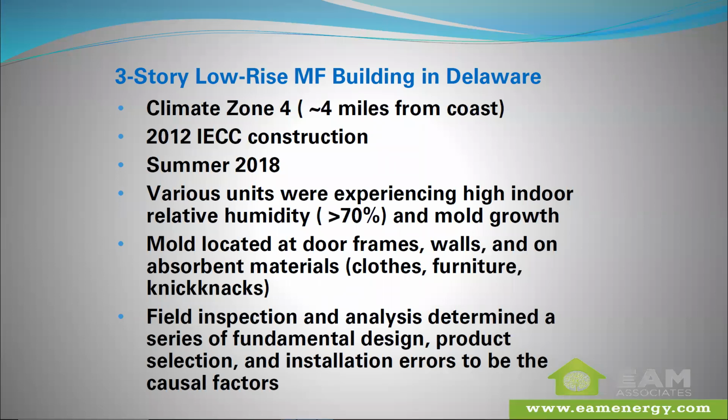When I was brought in to consult, various units in the building, this is a multi-building project, so you had issues in apartments across different buildings that were having very high indoor relative humidity above 70%, so uncomfortable. And that was also activating mold growth.